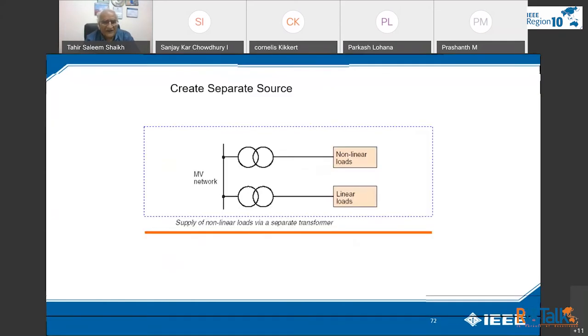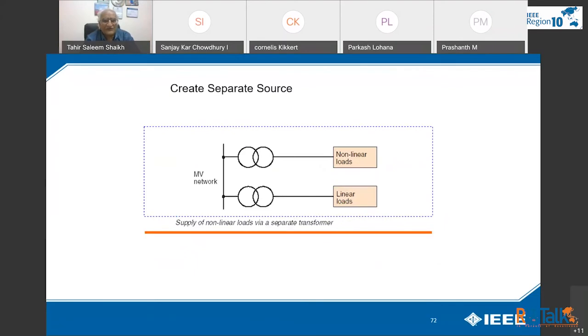The third would be that you have a separate source for non-linear loads and linear loads, which I've seen in Karachi, a problem in a foundry. In a foundry, I found this phenomenon with the induction furnace. They connected the non-linear load and linear load on a single bus bar. The source is 11 kV, the medium voltage, and there was a lot of problem for that. So they had to separate this source of power, the MV network, into two sources. They had to do it, and then the non-linear loads will have a separate panel and the linear loads will have a separate panel.